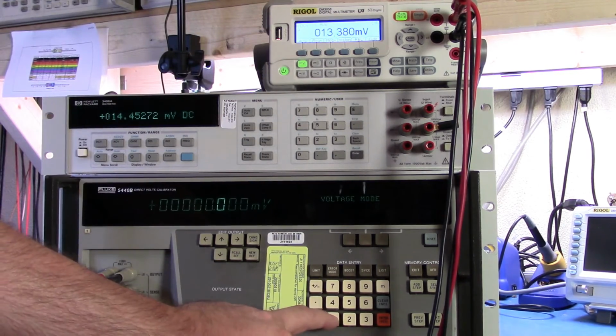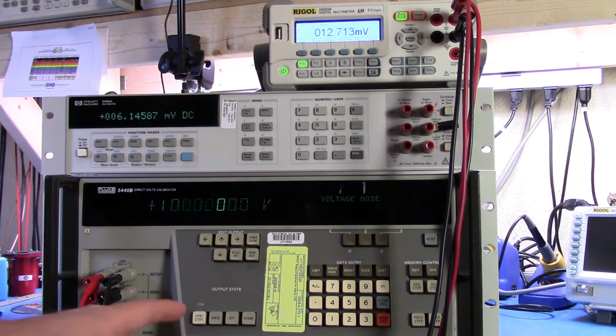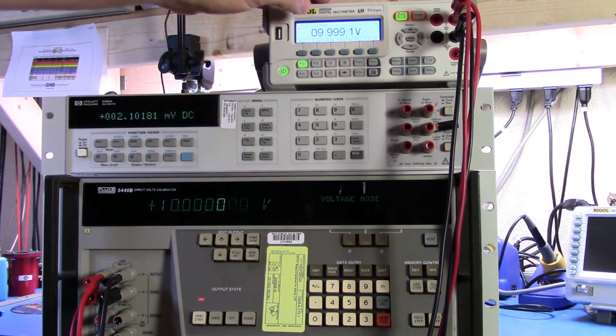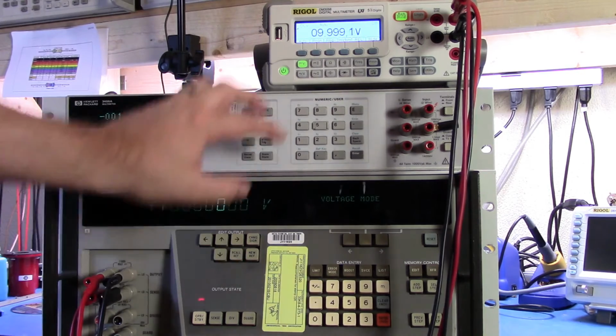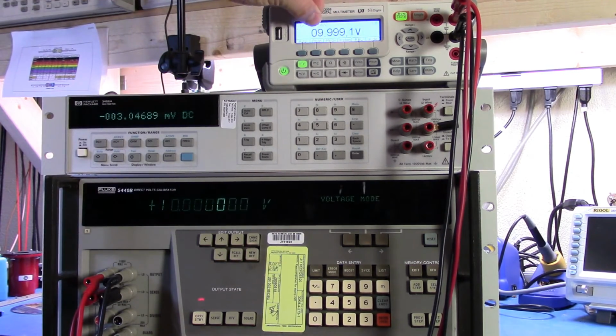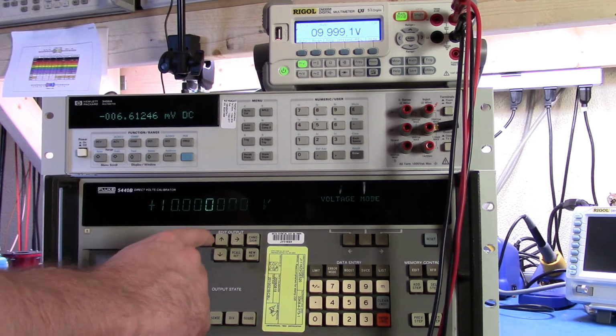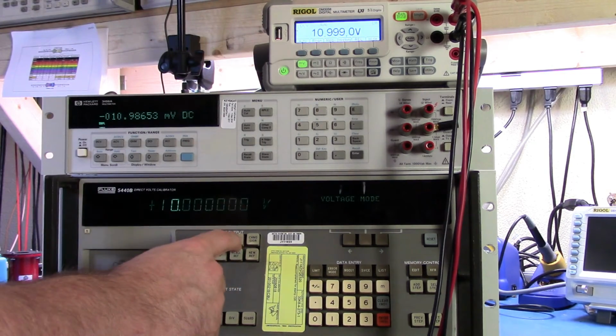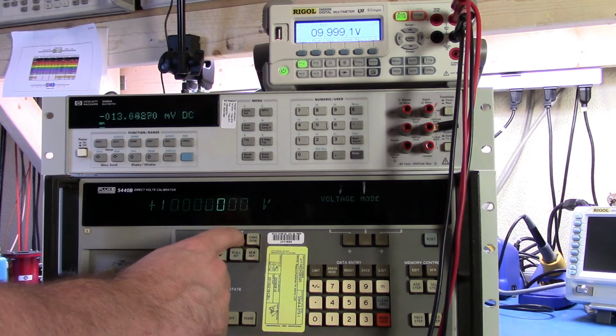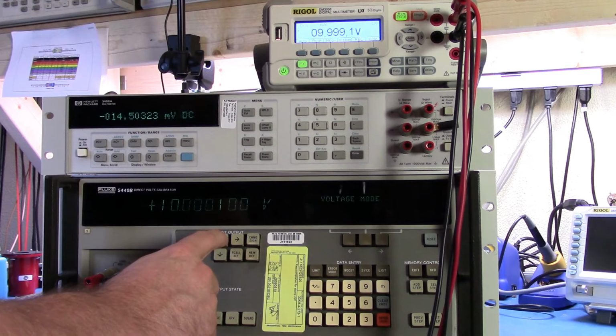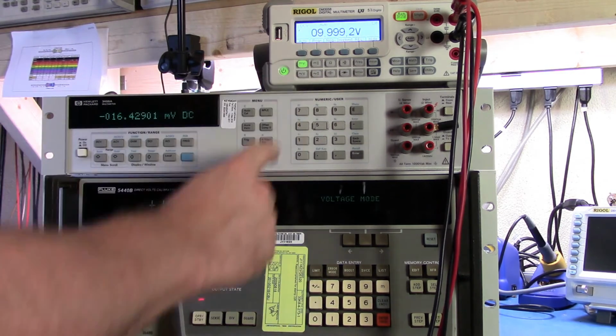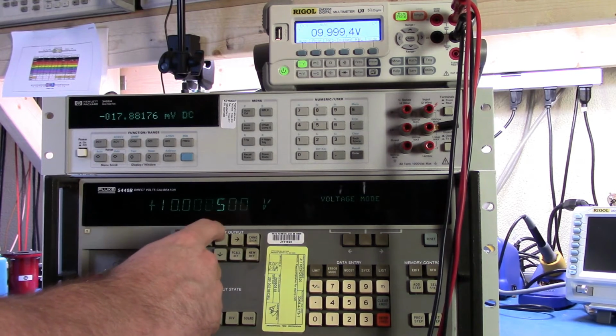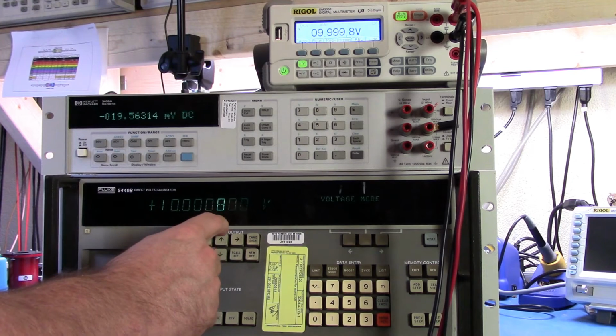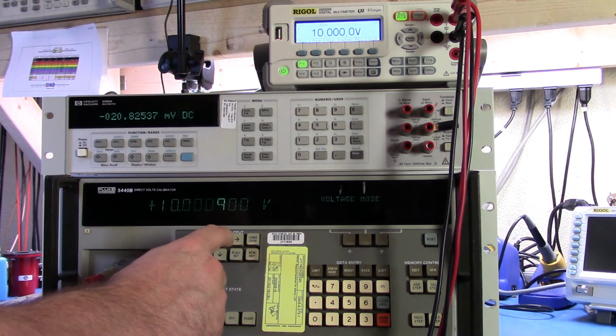So now I could go in and set 10 volts, and I could turn it on, and I could see what the voltage is on my meter. Now, because this would be highly calibrated, I can go, okay, I want this to show 10 volts. So I can use these keys to move this value around, and you can see that the value will change there. I think I need to increase this a little bit here, and so you can see that as I go up, it's starting to get me to 10 volts there, and there you go.